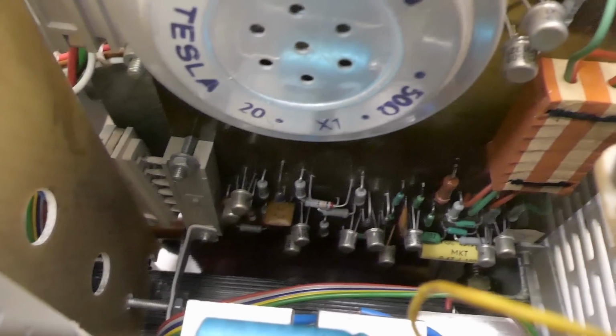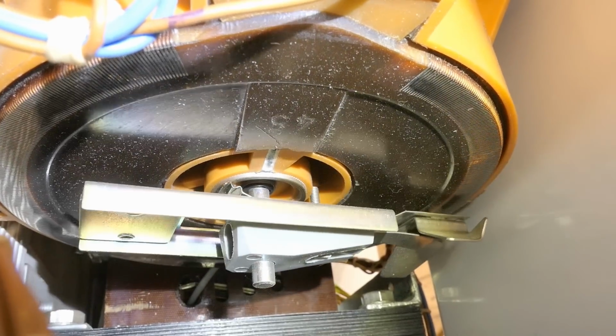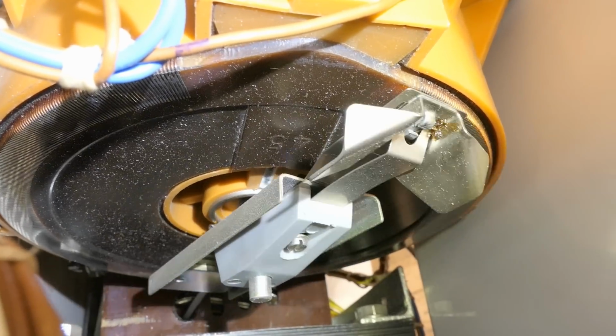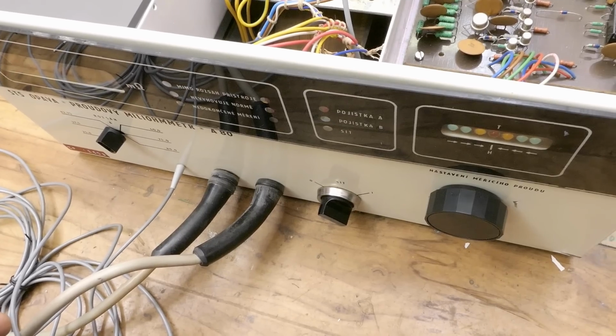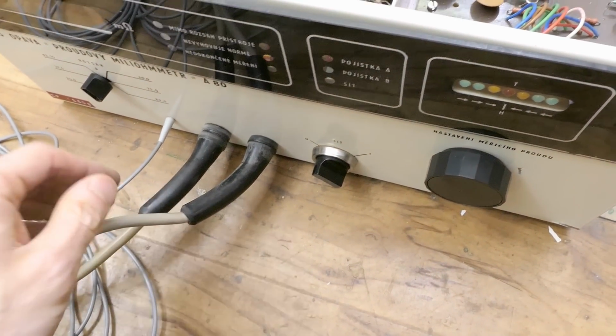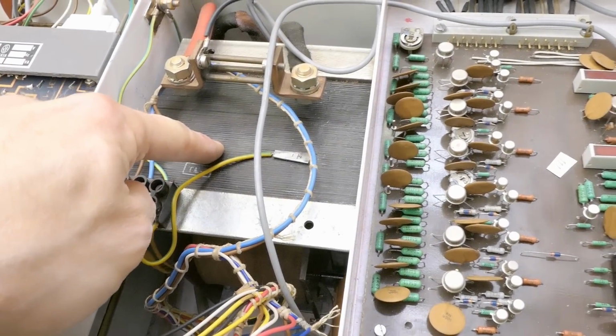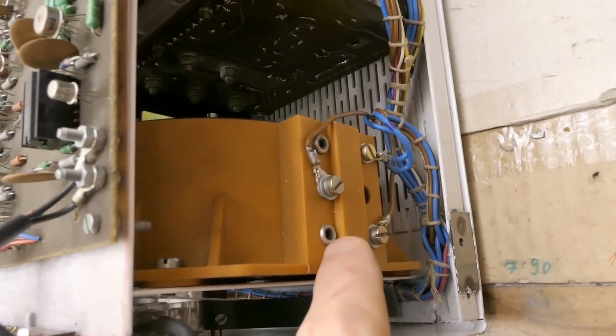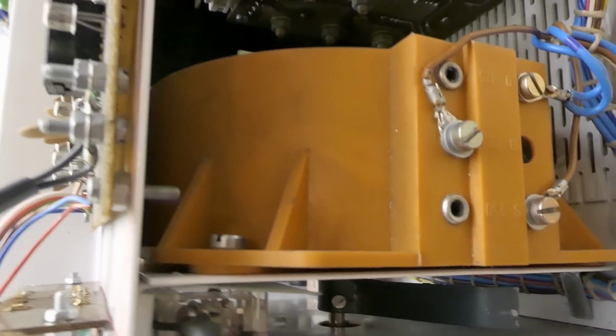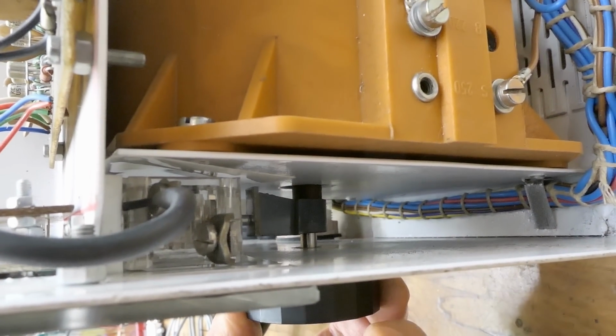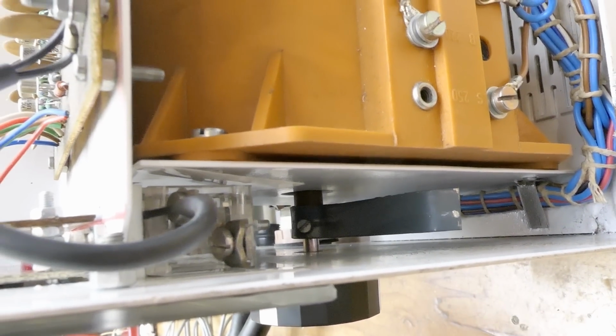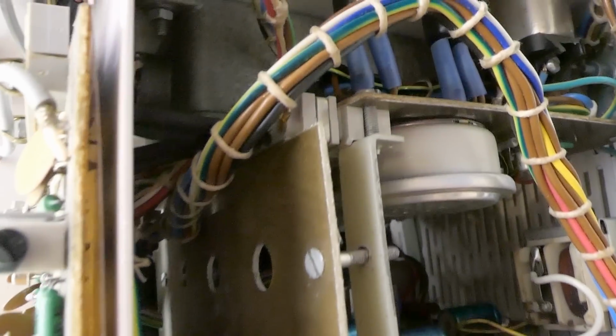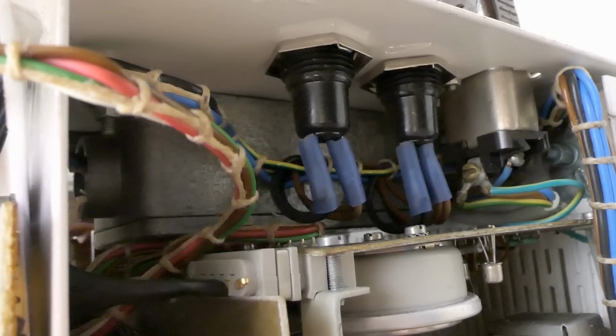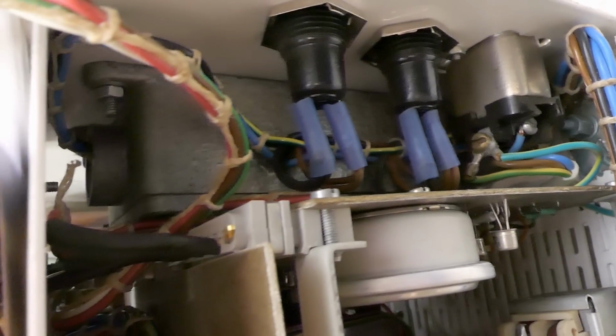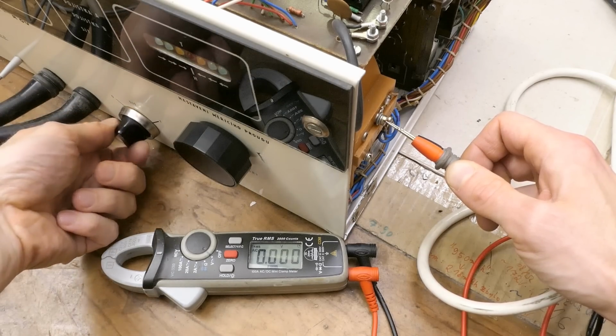This is bloody complex. Here's the slider of the variac sliding on the winding, and the slider has to have some heat sink, I guess. But why does it not produce any current here? I guess this transformer has a primary which has to go into the variac, and the variac is connected to the mains, probably not straight through this switch, but through some contactor. Where could the contactor be? There's a big metal box in it here, measuring the voltage of the variac inlet.